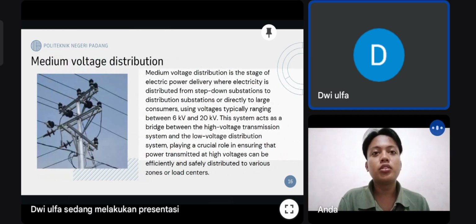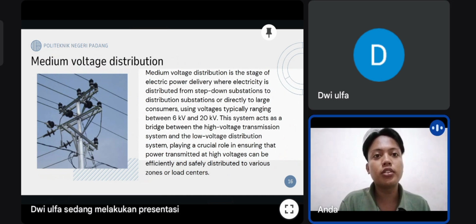Medium voltage distribution. Medium voltage distribution is the stage of electrical power delivery where electricity is distributed from the step-down substation to distribution substations or directly to large consumers using voltages typically ranging between 6 kV and 20 kV. The system acts as a bridge between the high voltage transmission system and the low voltage distribution system, playing a crucial role in ensuring that power transmitted at high voltage can be efficiently and safely distributed to various zones or load centers.